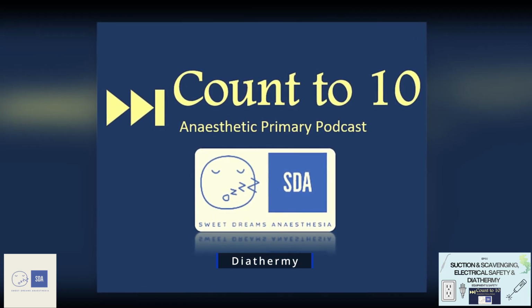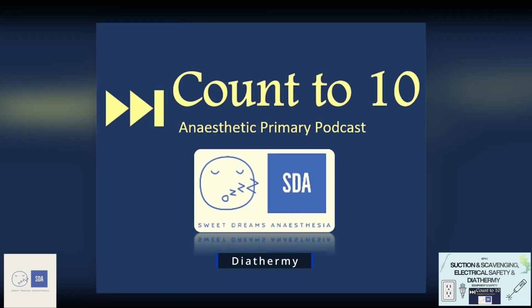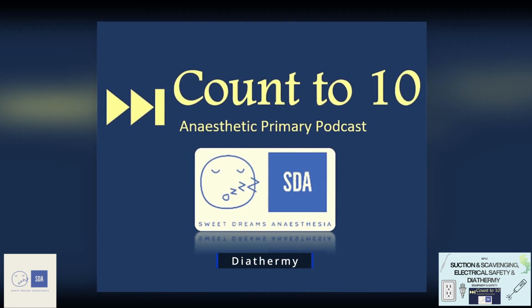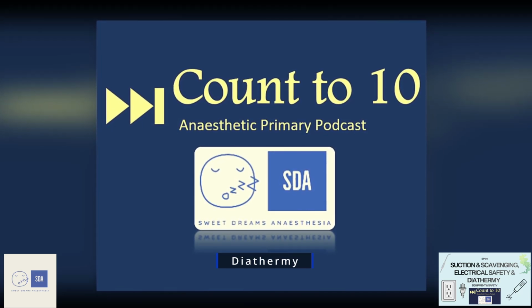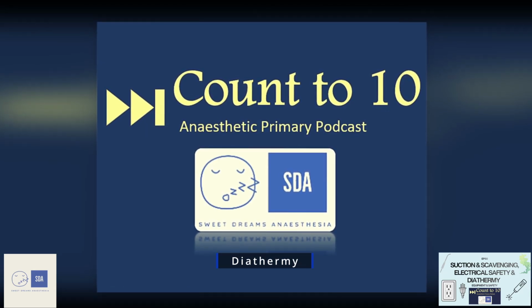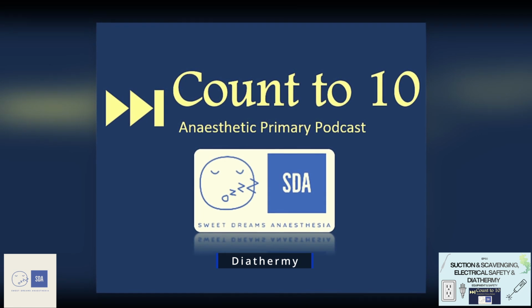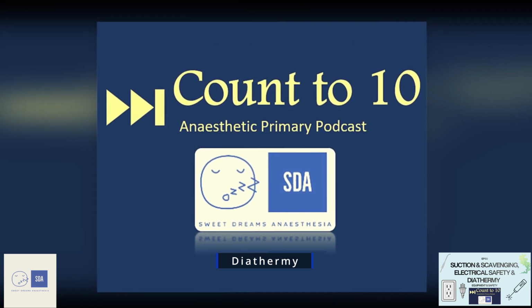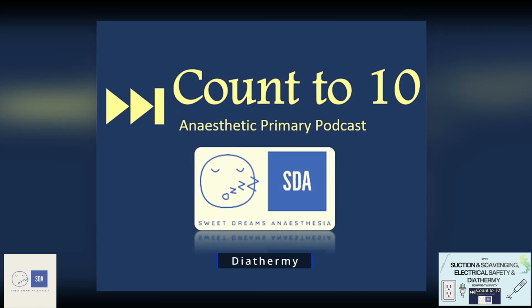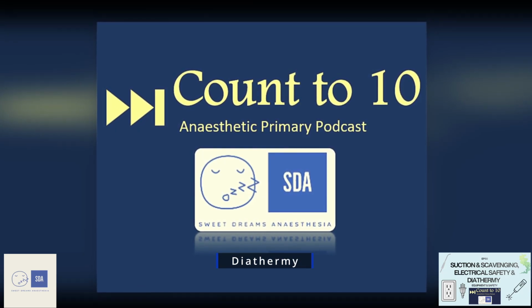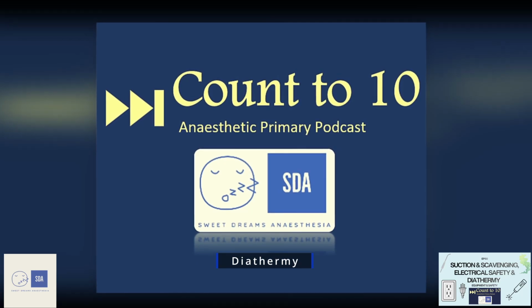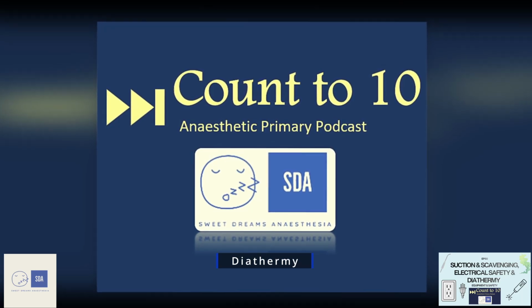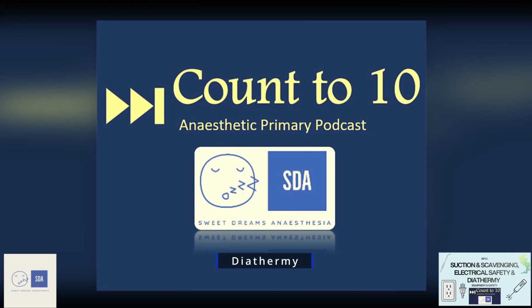A diathermy is a device that's used to pass electrical current through tissues to generate heat in order to coagulate blood vessels or cut and destroy them. The mechanism of action behind this is that it uses AC current at really high frequency, close to 0.5 to 2 megahertz, to generate heat within these tissues. The heat that's generated is proportional to the electrical power that's dissipated, and typically the electrical power behind these diathermy devices is close to 50 to 400 watts.